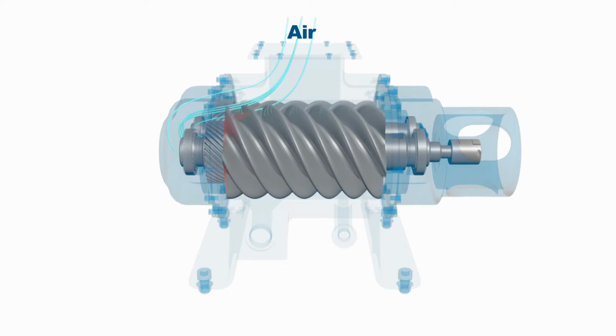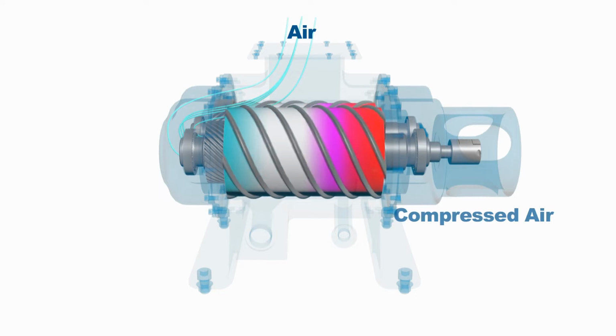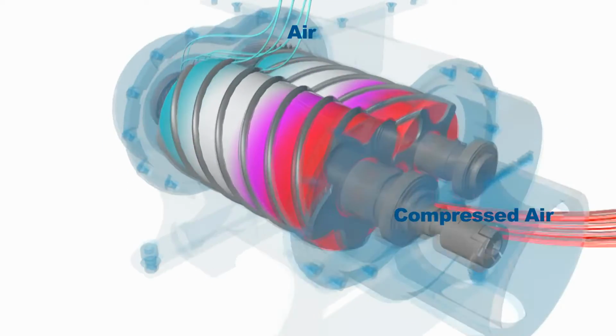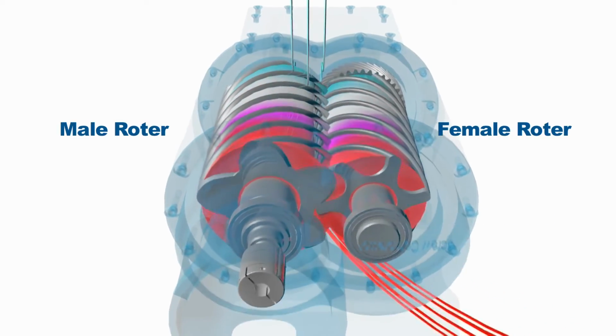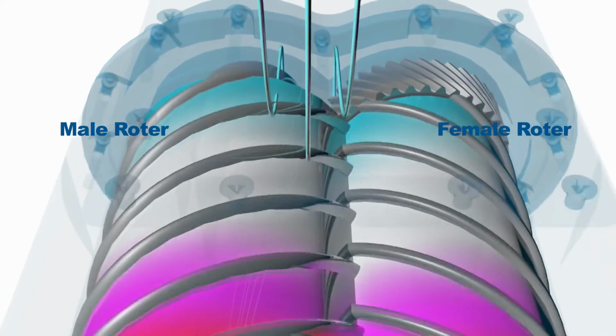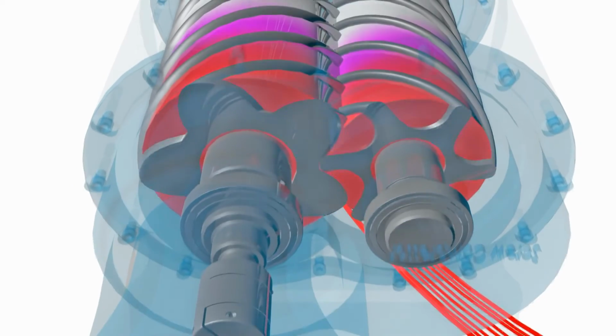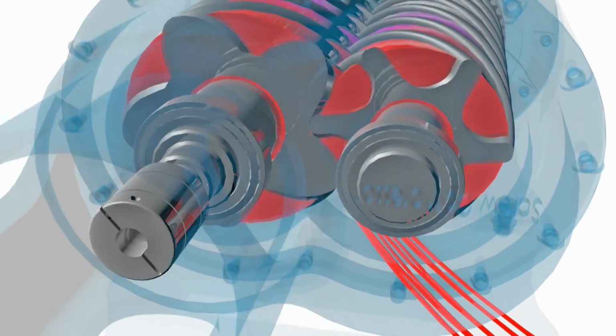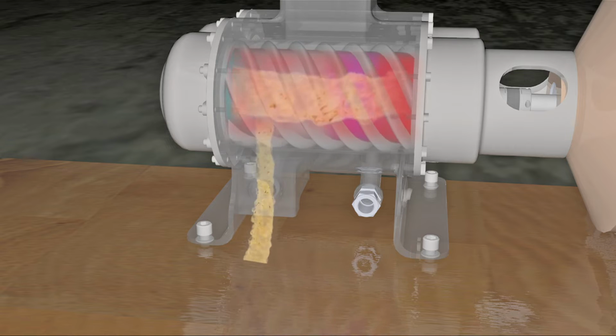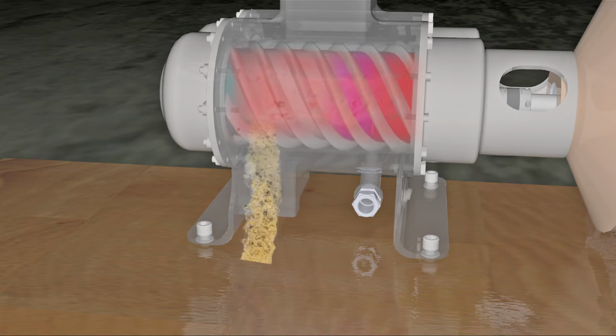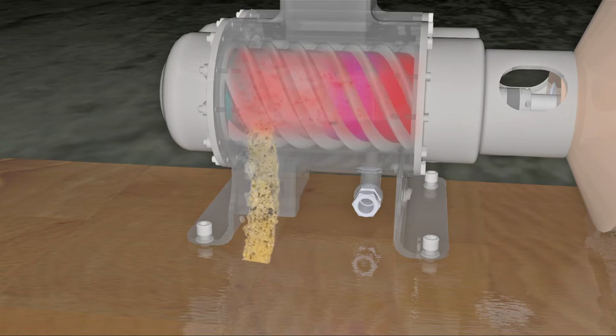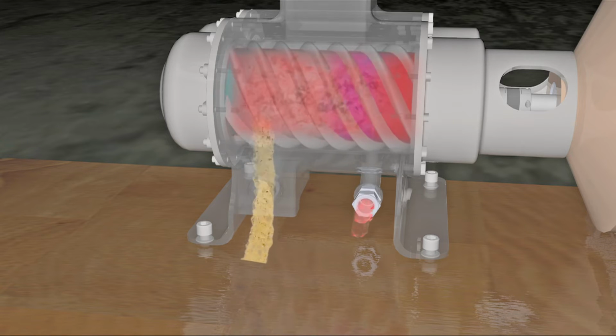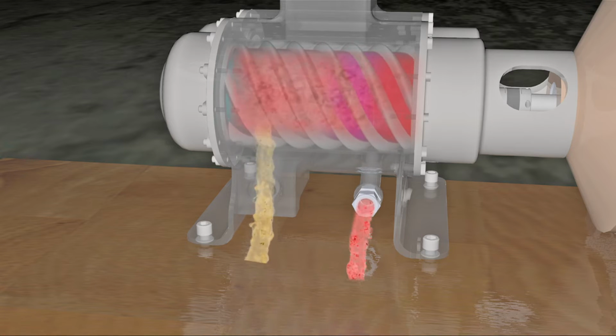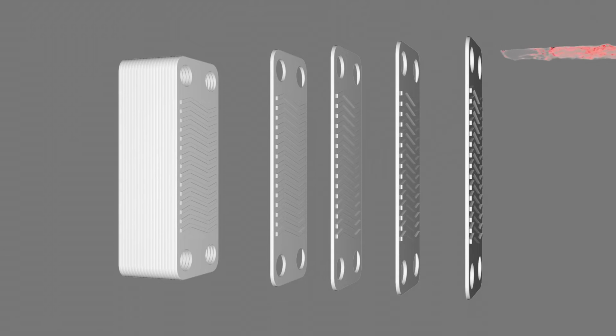The basic principle of a screw compressor is as the male and female rotors rotate in opposite direction, they draw air in between them. As this air progresses along the rotors, it is compressed as per the decreasing volume space between the rotors. This creates the compressed air that is displaced to the outlet. As a subsequent process, when air is compressed, heat is generated. This heats up the cooling oil, which is lubricating the compressor at the same time. The mixture of hot oil and hot air flows towards the oil and air separator from the screw element and then gets directed towards the heat exchanger unit through the left pipe.